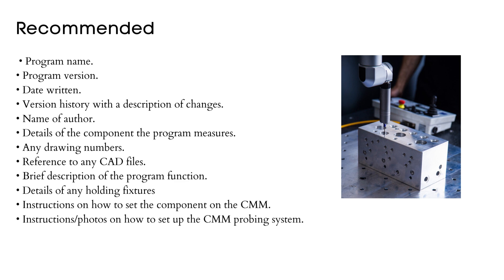Programs should also include any drawing numbers, reference to any CAD files, a brief description of the program function, details of any holding fixtures, instructions on how to set the component on the CMM, and instructions or photos on how to set up the CMM probing system.